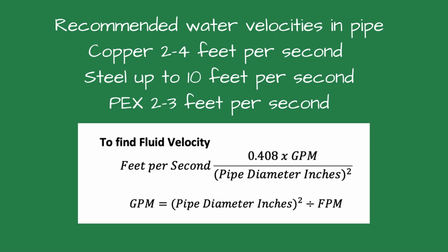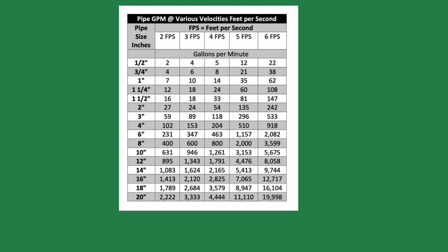The recommended velocity guidelines are: copper pipe use 2 to 4 feet per second, steel pipe up to 10 feet per second. A system design rule of thumb is 2 to 4 feet per second is ideal for comfort and longevity. PEX is typically 2 to 3 feet per second.